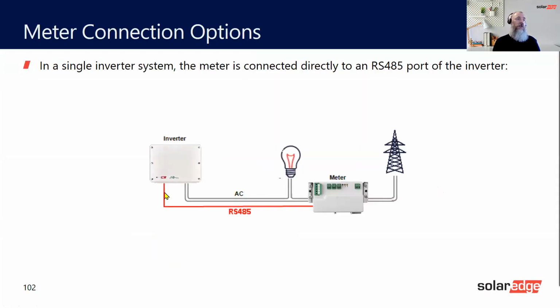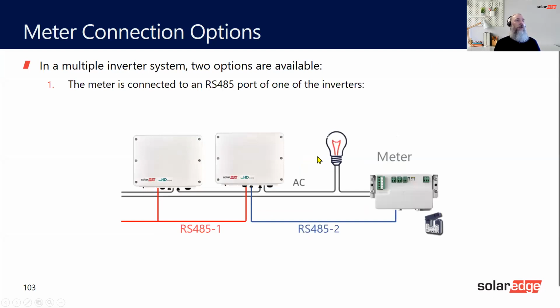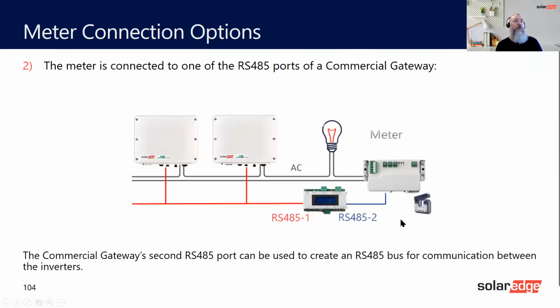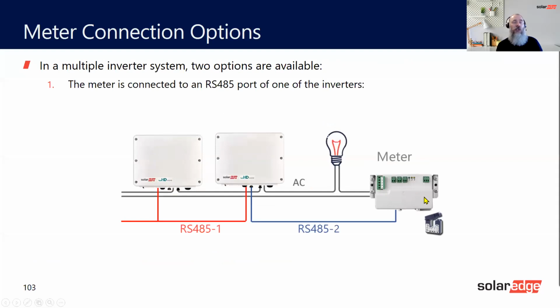So the connection options, RS485 here, obviously it goes to this one here. We spoke about RS485 cable and Cat5 and Cat6 and which one's better. You can see on here how we've got RS485 with leader and follower on one bus, and then the meter is on the other bus. So RS485-1 and RS485-2. Both of them are supported. And remember to do the dip switches for end of line for both of them. So if it's the leader, you must do the end of line dip switch, and the very last follower, you must do the dip switch. And the same for here. You'll see the dip switches later on. This has a dip switch on it, and the inverter has a dip switch as well.